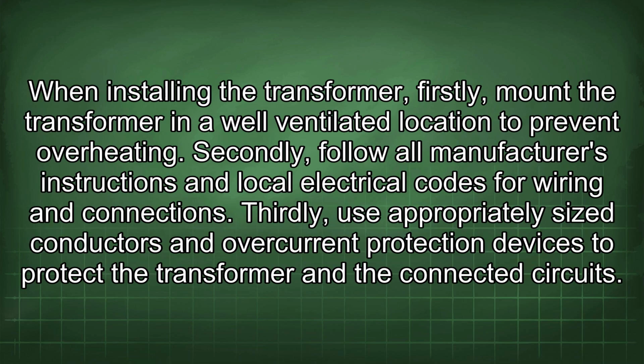When installing the transformer, firstly mount the transformer in a well-ventilated location to prevent overheating. Secondly, follow all manufacturer's instructions and local electrical codes for wiring and connections. Thirdly, use appropriately sized conductors and overcurrent protection devices to protect the transformer and the connected circuits.